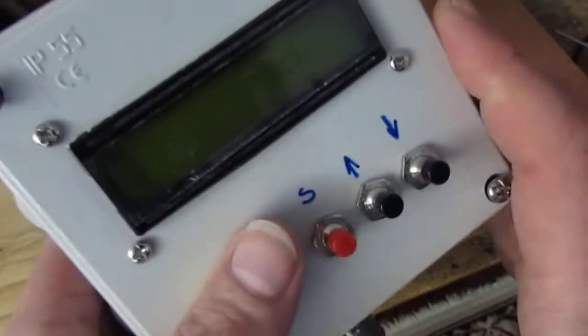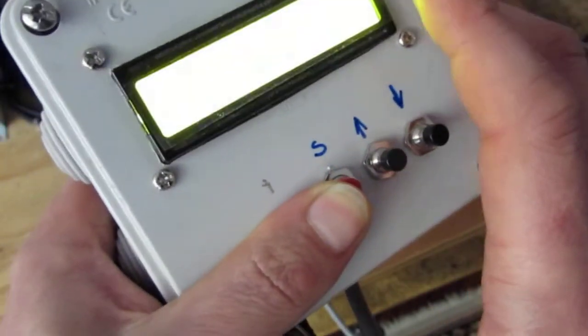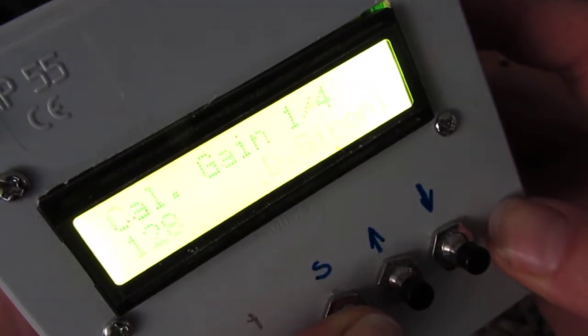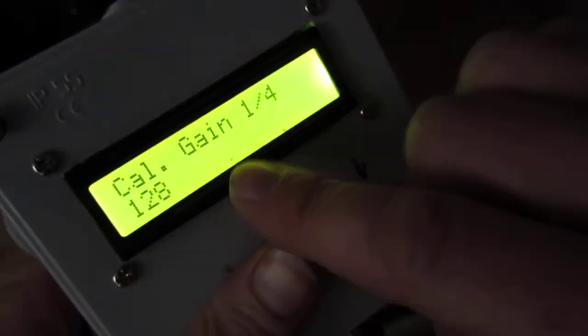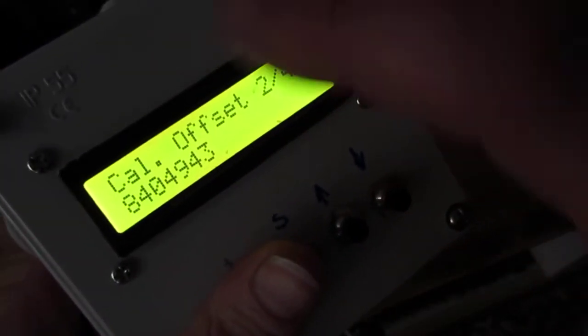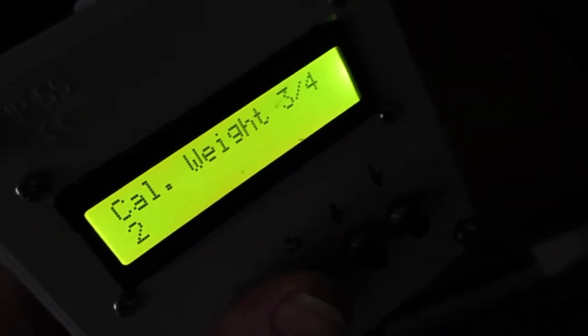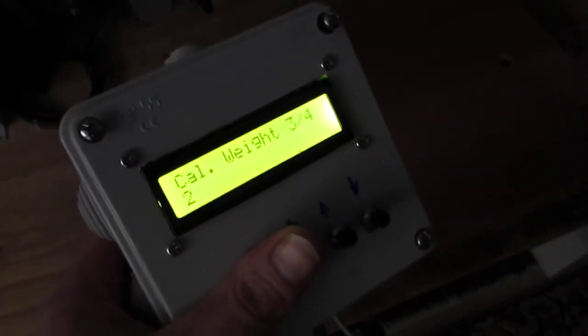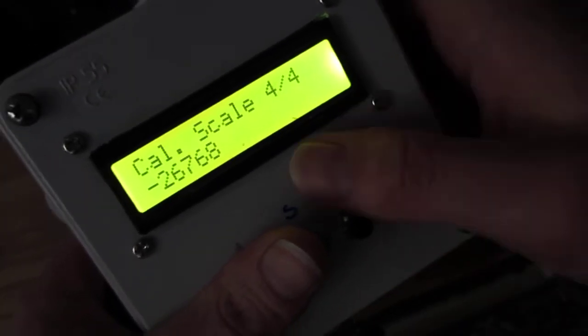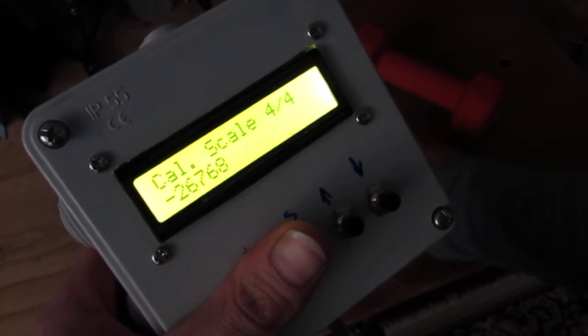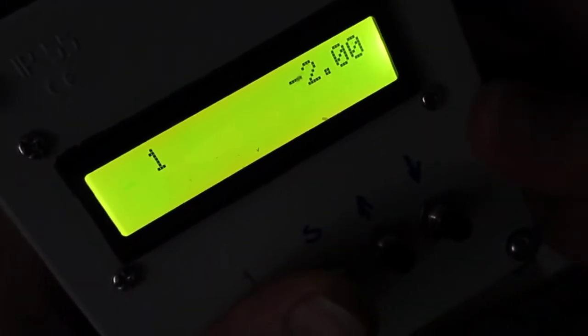In order to calibrate this device, we long press the select button while powering this on, and then long press this. We enter the calibration mode, where we have 4 steps. The first one is the gain selection, then the offset, that is the tare of the scale, and the calibration weight. I used this weight to calibrate this model, and then I have to long press this while this weight is on top of the plate, to calibrate the device. And then I long press this and I save all the values. So let's set the tare to 0 and we are good to go.